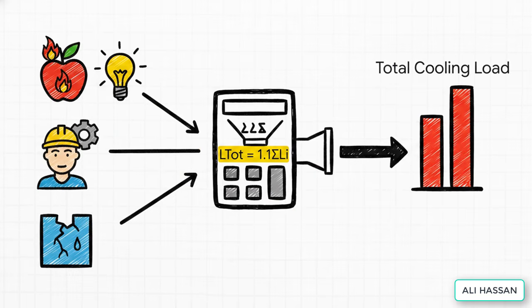After they have painstakingly calculated every one of those heat sources, the walls, the product, the people, the lights, they add it all together. They sum it all up, add a little safety factor just in case, and they get one single critical number, the total cooling load. That number tells them everything. It determines how big the compressor needs to be, how much refrigerant they need. The design of the entire system is based on that number.